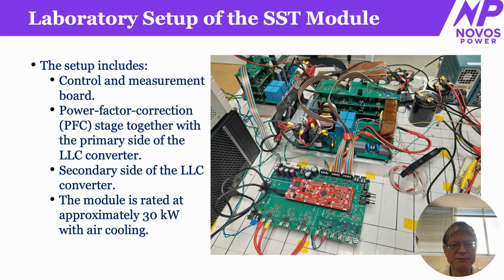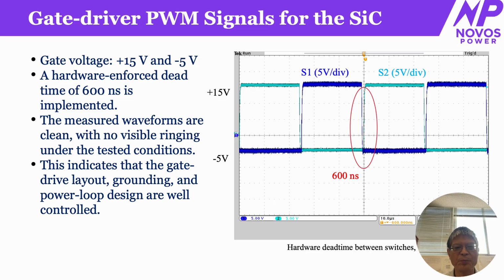In the last few months, we have been able to do a laboratory setup. Over here, you can see the system setup, the primary, the secondary, and also the isolation transformer. By doing that, we did, for example, the testing at the device level with nanoseconds, and you can see the switching waveforms are almost perfect without much noise in there. I want to also mention that we have not incorporated our optical fiber communication yet. You can already see a good waveform. By doing the future design with optical fiber, you will have a much better waveform as well.